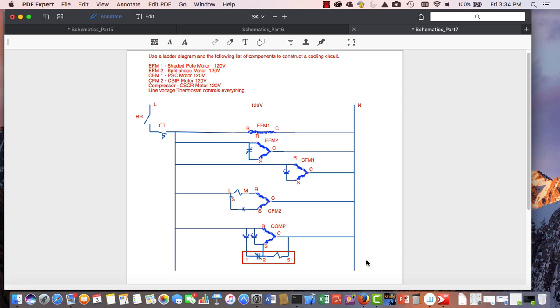This is a standard cooling circuit that you will find in something like a flower cooler, or a more medium to high temperature piece of equipment where we cycle the evaporator fans on and off. By the way, the trainers in the Porter and Chester shops have, for the most part, 2 EFM motors if there are 2 motors on the evaporator fans, and they'll be shaded poles.